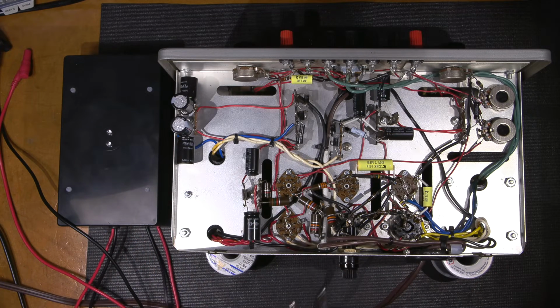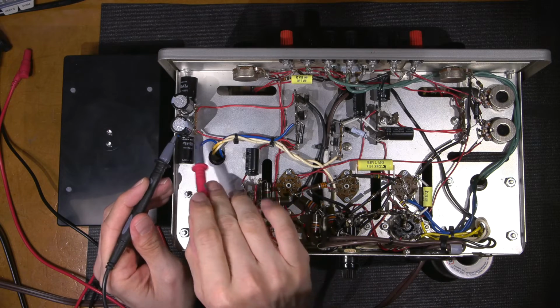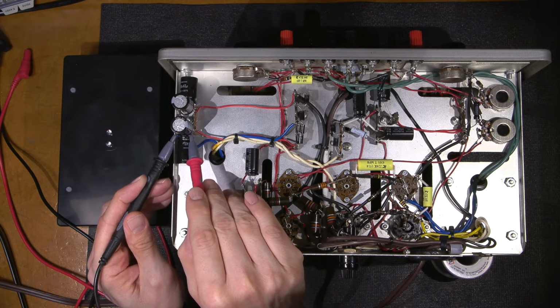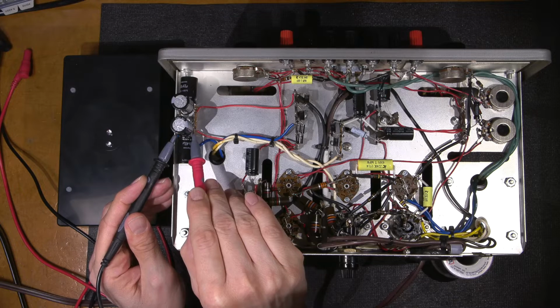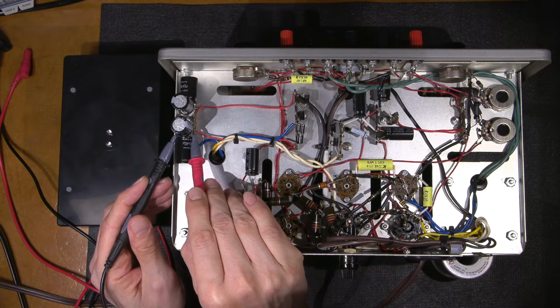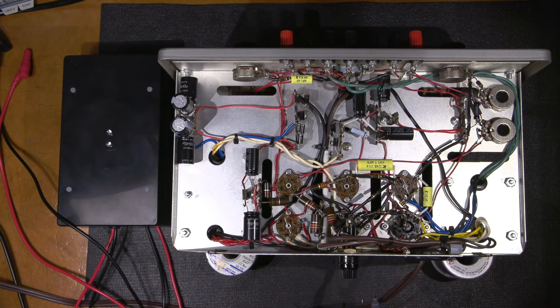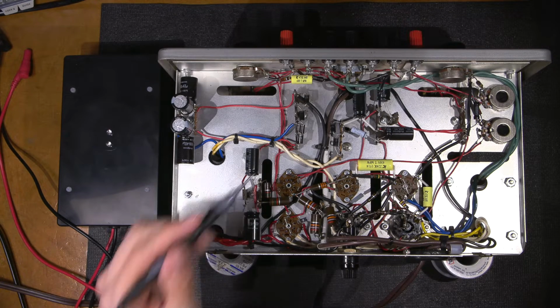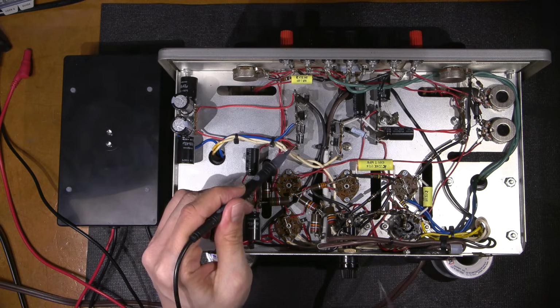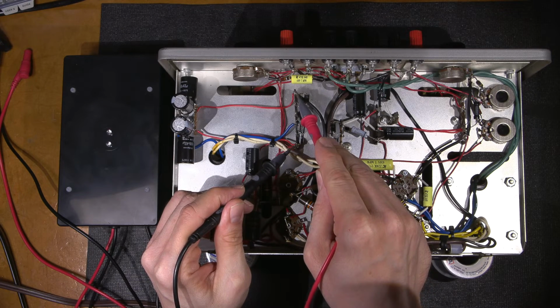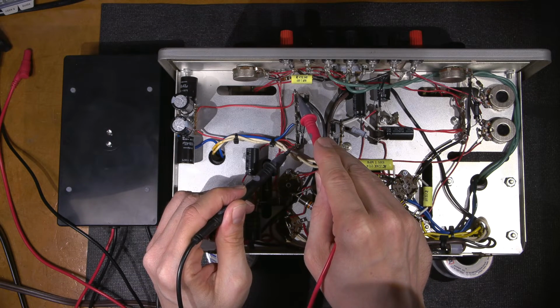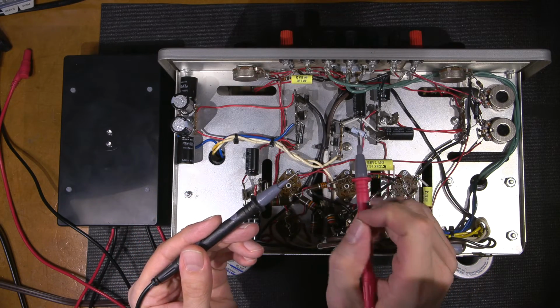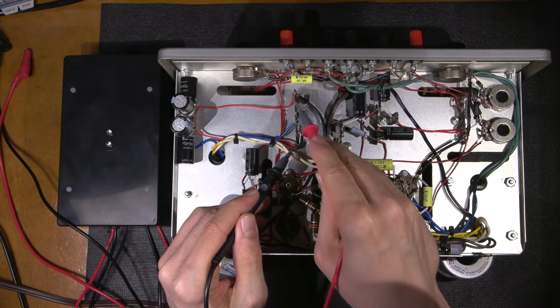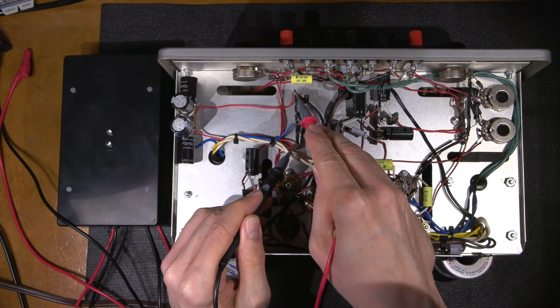Now you'll see me when I'm going across a capacitor in a unit like this, I'm doing this with the probes. I'm using a sawing motion. The reason that I do that is to ensure that I have a really good connection. If there's any type of debris on the leads, if you're going across terminals like this, and you just touch them, a lot of the times there'll be flux residue or something under there that will stop the connection. This is a pretty shiny, polished surface on these probes, right? So you want to make sure that you're moving the probes around like this to make sure that you get that good connection.